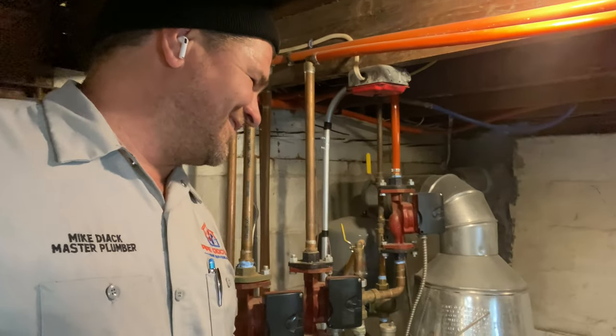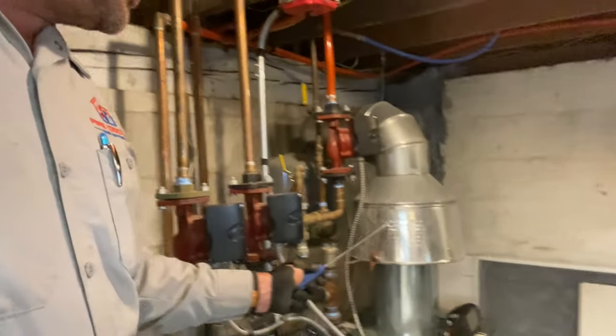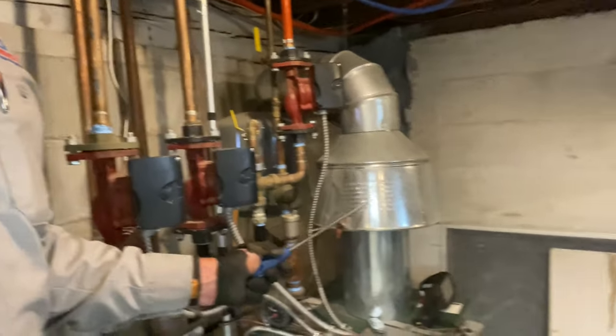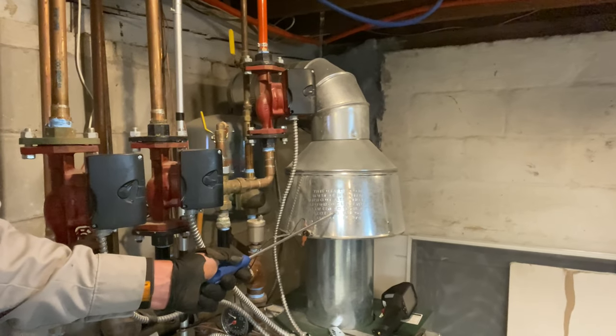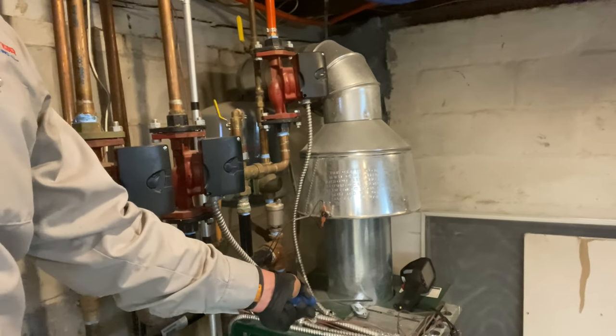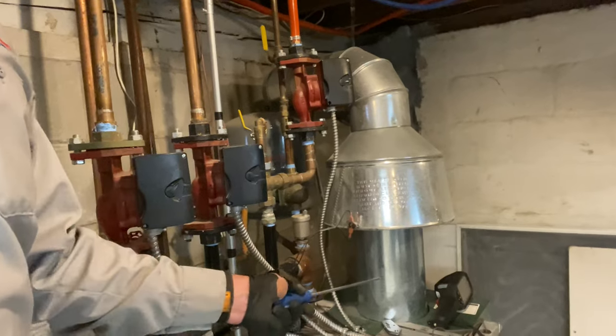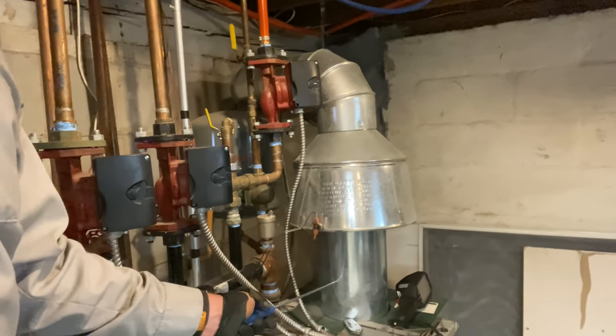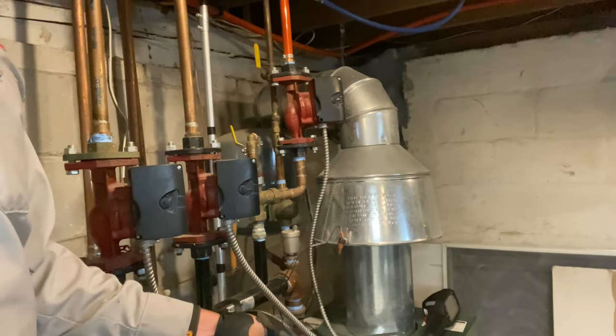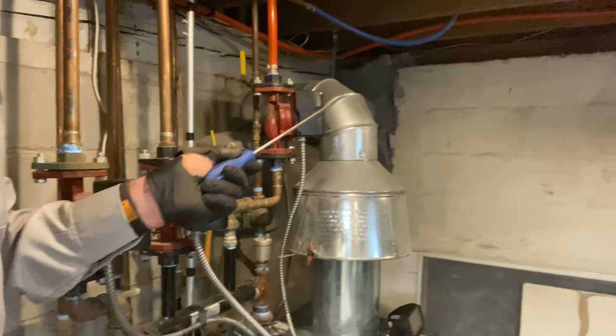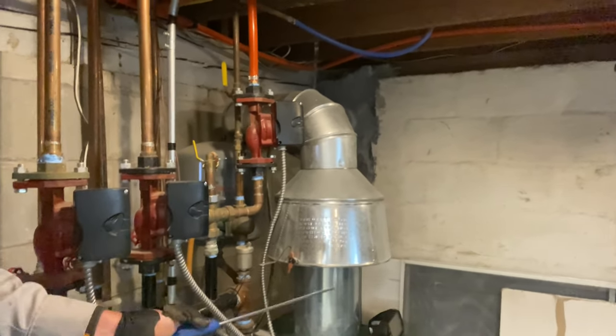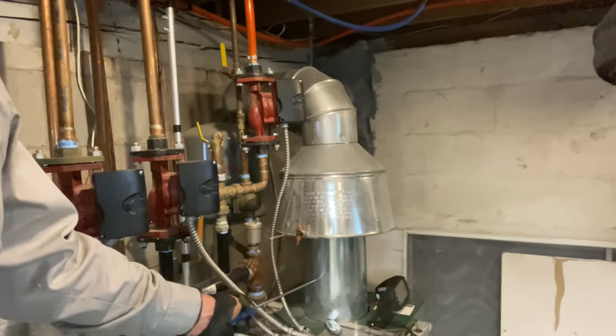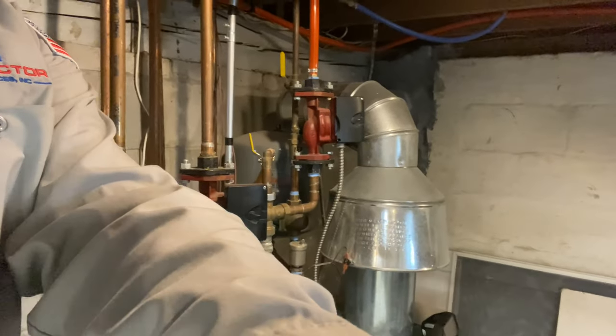This draft hood, by the way, shall never, ever, ever be modified. What that means is do not cut this down, do not modify it. We could drill a hole in it to do a combustion analysis, but it shall never be cut down in order for it to fit to a flue. Never, ever, ever. So when you drill a hole in it, that's for testing combustion, which we're going to do next. That's why the combustion analyzer is right over there.